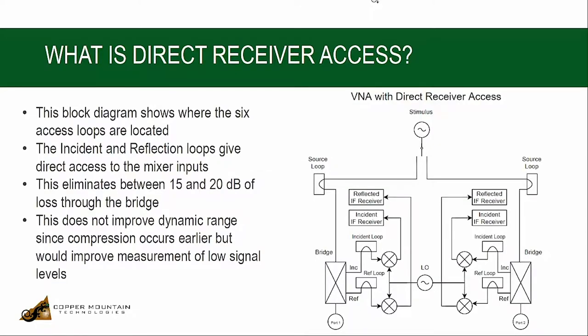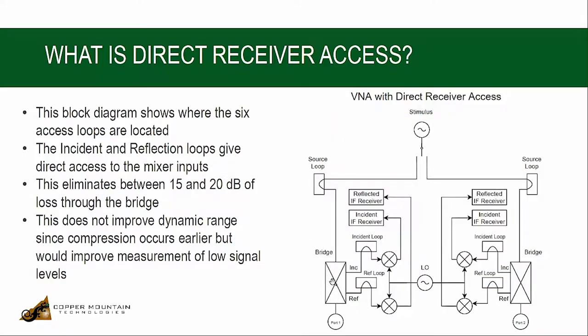Here's a block diagram of a VNA showing the stimulus at the top and it switches back and forth from port 1 to port 2. Imagine it's connected to port 1, then the stimulus passes through the source loop, and that's the middle loop on the left-hand side. It then passes through the measurement bridge, which is inside the VNA, and out port 1.